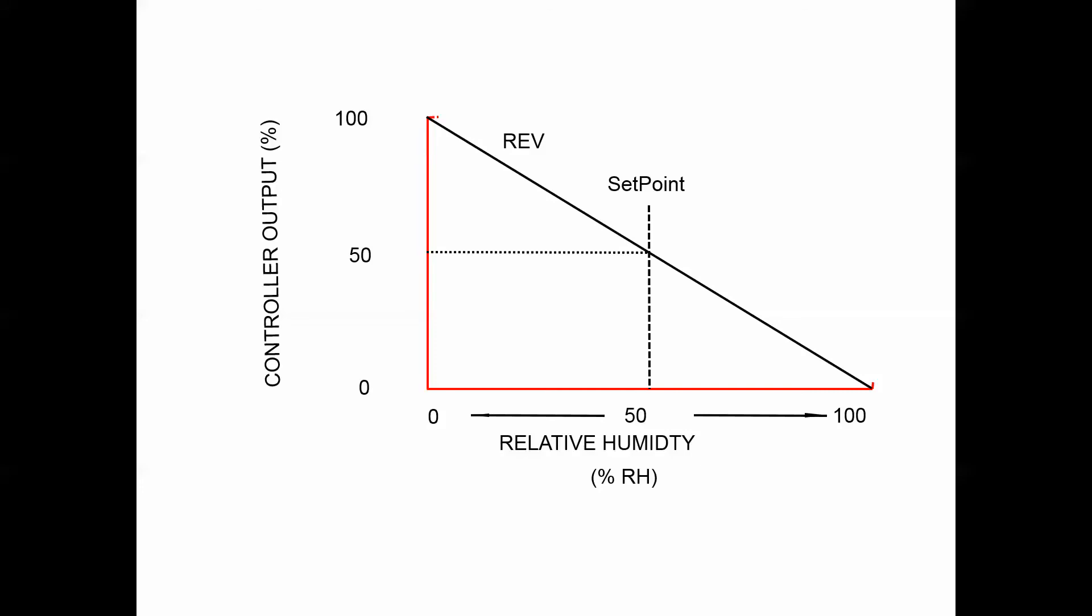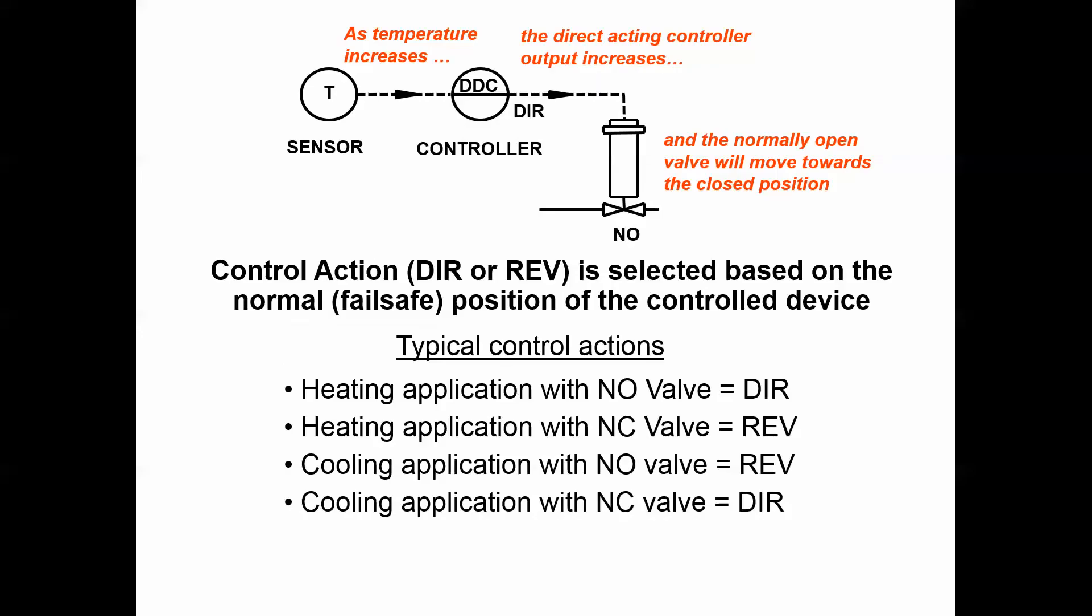Why is that important? You may notice on some of our control drawings we'll see notation like this that indicates where you have a direct acting control signal and something like a normally open control valve. As an example, if you have a heating valve and you want it to fail open to prevent some type of freezing condition or occupant discomfort, when you select a normally open valve you're selecting a valve that has a spring assembly such that a control output is going to take that valve position away from that normally open - it's going to start closing it.